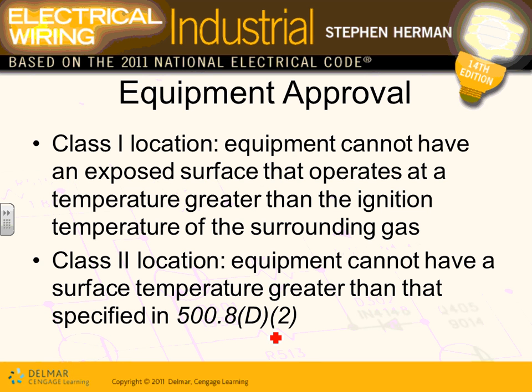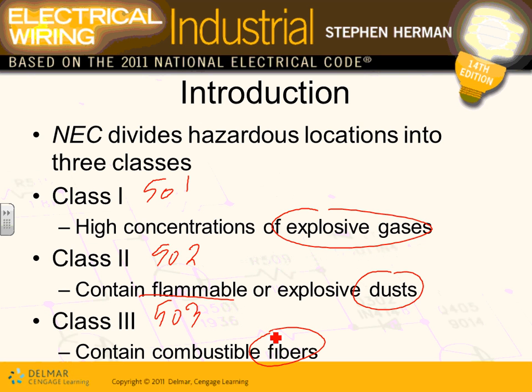So these are the three locations. Then there's Div 1 and Div 2, division. They call it Division 1, Div number 1, and Div number 2. Division 1, guys, the hazard exists at all times. Division number 2, the hazard exists under abnormal conditions. So if you have a gas spill, that's an abnormal condition. That's Division 2. The hazard exists at all times, like inside the gas tank. I mean, do you want to put a switch inside the gas tank and ignite it? That hazard exists at all times. But around the gas tank, there is no hazard. But the hazard could exist under abnormal conditions, which is Division 2.